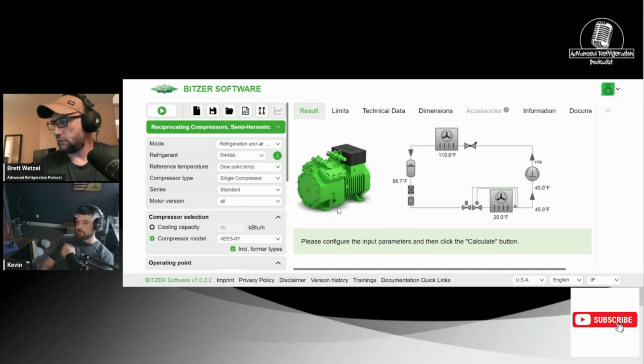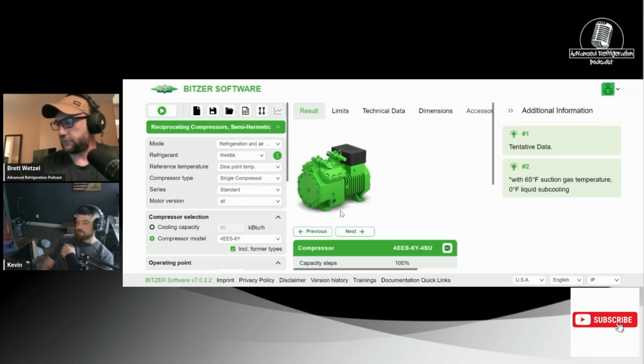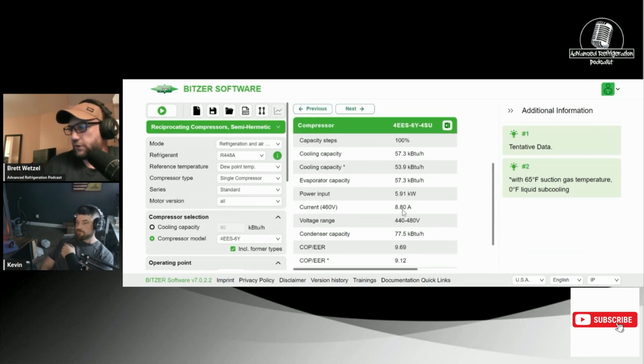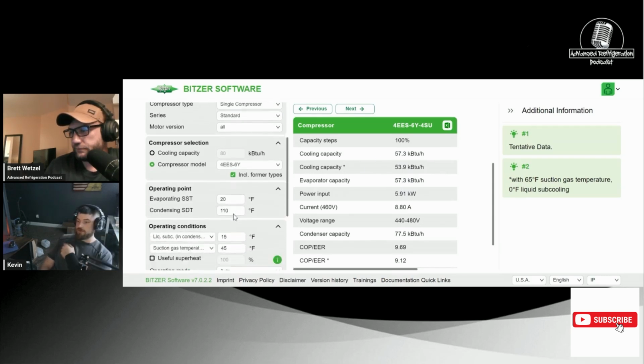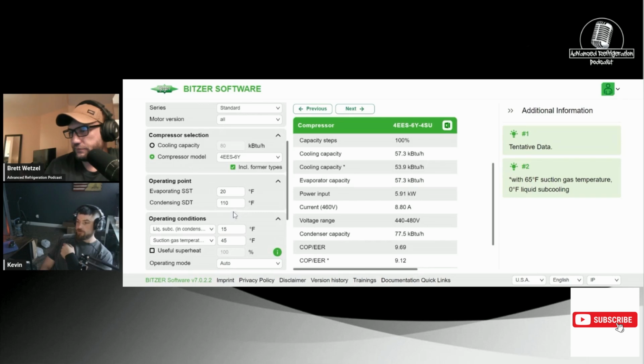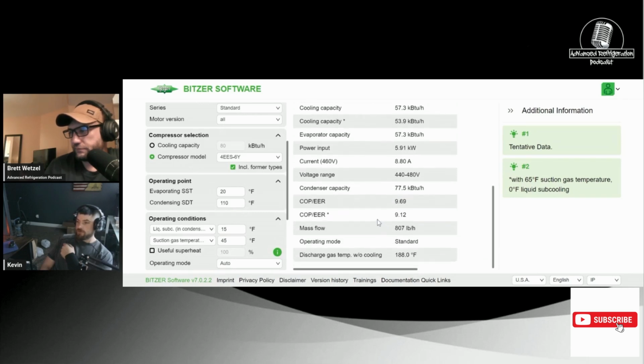Hit the start button. No, I'm trying. Just being stupid. All right, now we're still at 8.8, and look, our cooling capacity actually went up because it was at 53.9, right? Yep, and that is from lowering that suction gas. It's more dense, so the compressor is more efficient. Now, if you look down there, our efficiency went up a little bit, and also the discharge temp dropped from 208 down to 188 degrees.